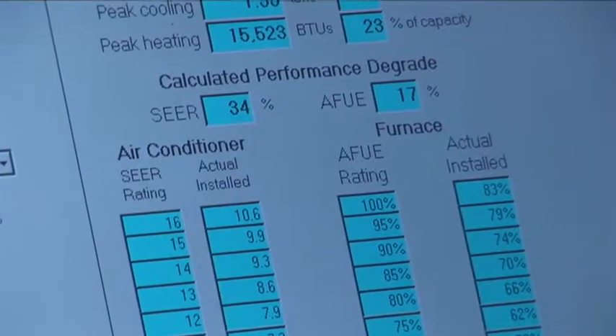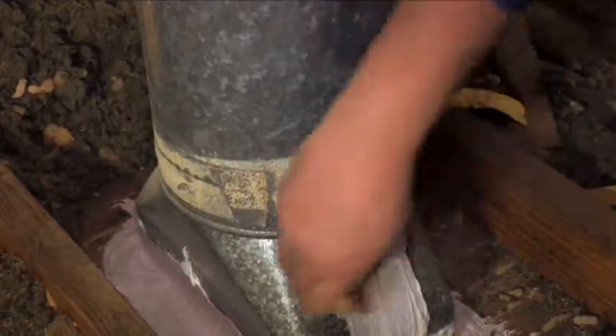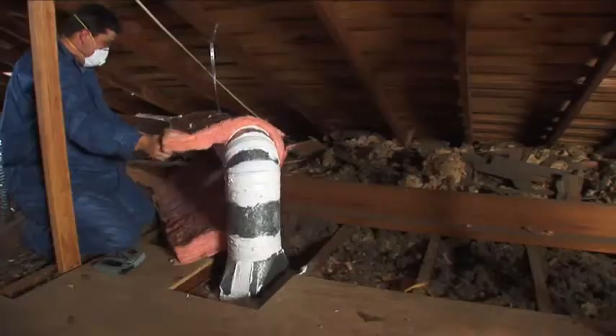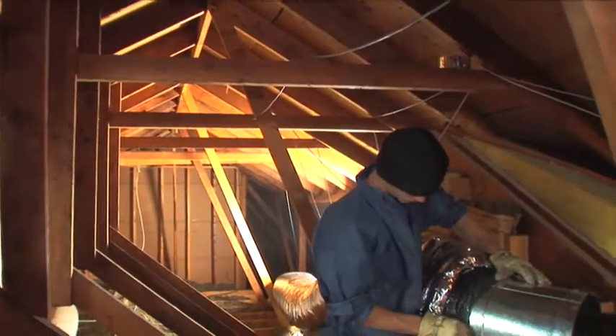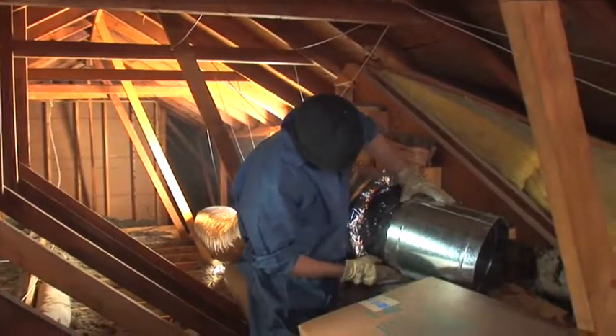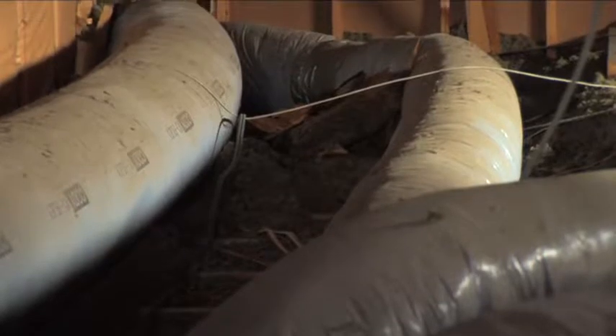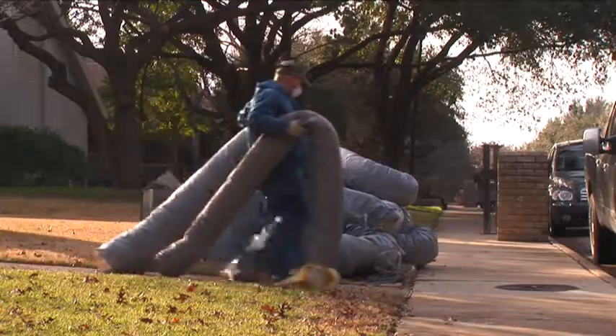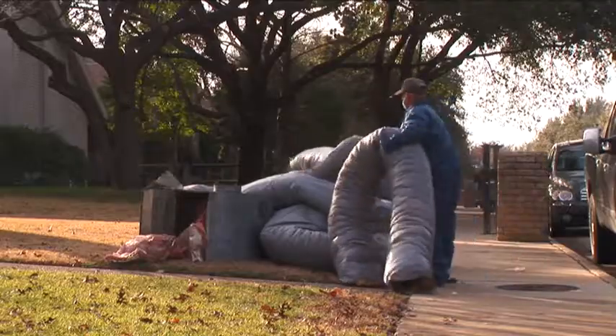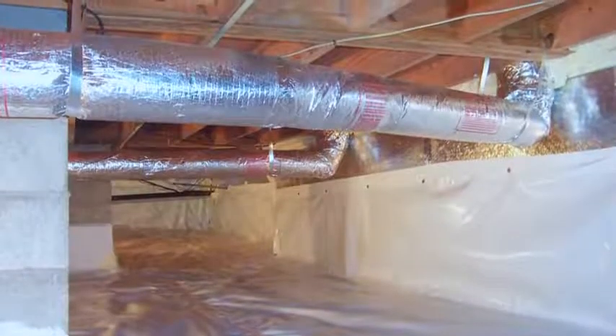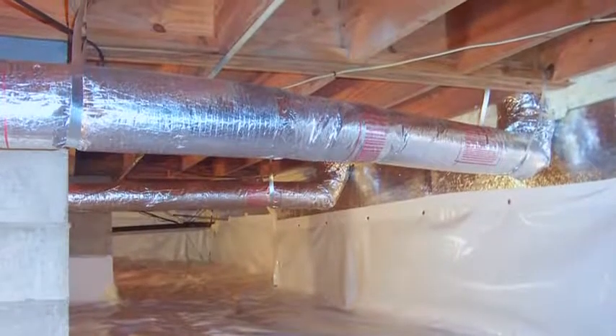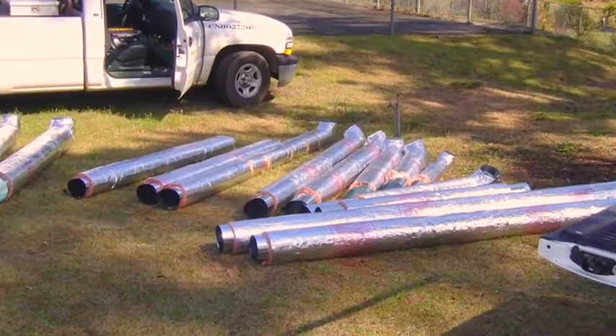After evaluating your current duct system, your consultant will prepare an upgrade plan. Now, most duct systems can be greatly improved by performing a comprehensive duct renovation. Usually you can get by replacing sections, insulating, sealing, that sort of thing. And yes, you might be able to add a little bit of return here and seal up these gaps and holes and try to straighten out the flex duct. But many times your best strategy will be to replace that duct system entirely with a new one that is designed correctly and wasn't installed 40 years ago by the contractor who had the least cost bid to do this work. There are a number of houses where you just can't fix the duct system that's there.